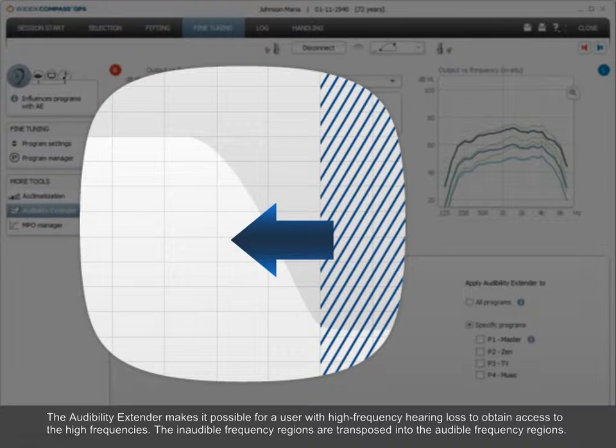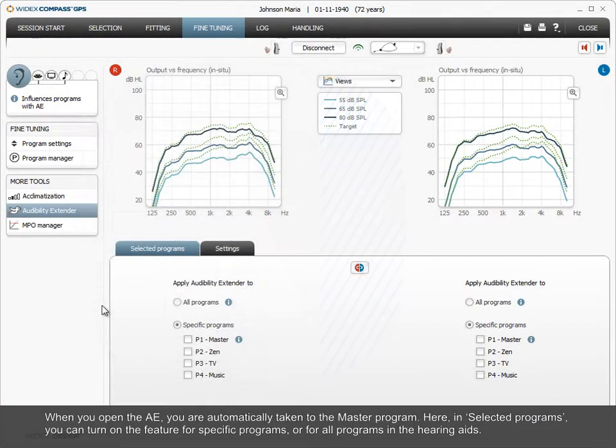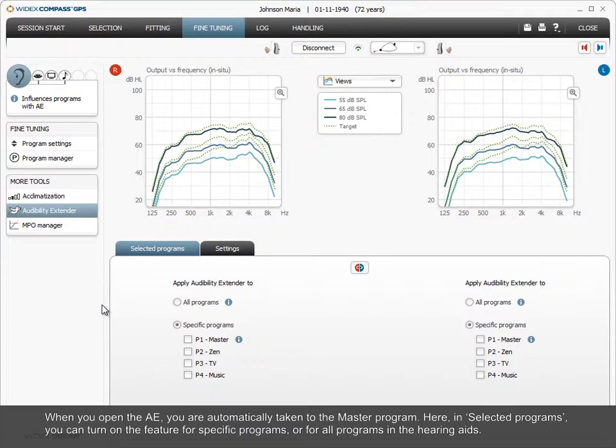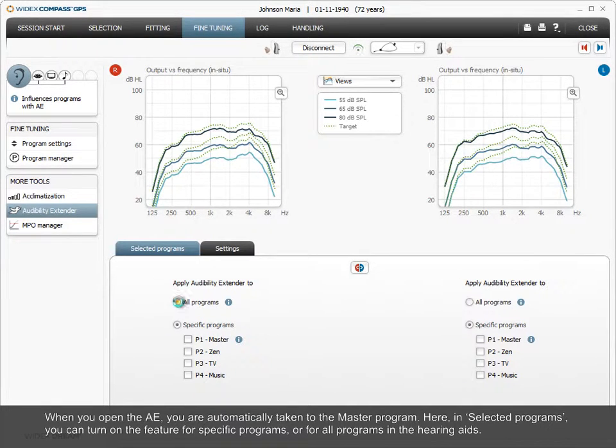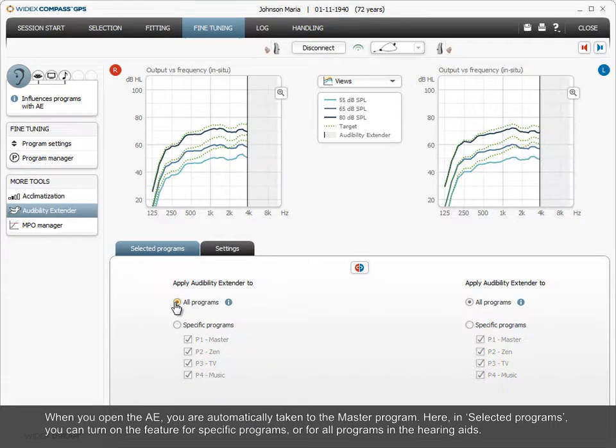The audibility extender makes it possible for a user with high-frequency hearing loss to obtain access to the high frequencies. The inaudible frequency regions are transposed into the audible frequency regions. When you open the AE, you are automatically taken to the master program. Here, in Selected Programs, you can turn on the feature for specific programs or for all programs in the hearing aids.